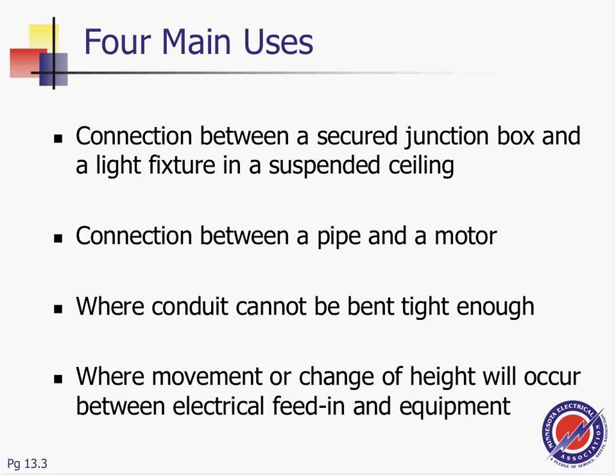A few things about the uses of flexible metallic conduit. So we'll jump directly, guys, into the uses of flexible metallic conduit. Between a junction box and a lighting fixture is very common. That's in a suspended ceiling. That's very common, probably with a lot of use. You don't want to use an MC cable. This is probably the most common application where you can use a flexible metallic conduit.